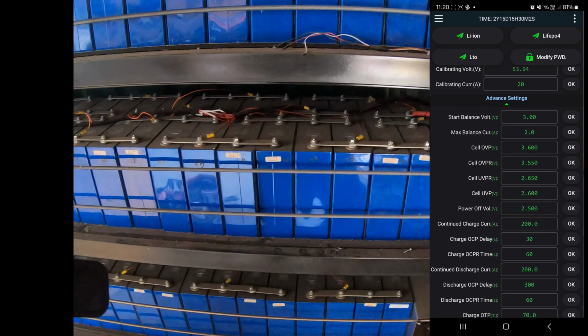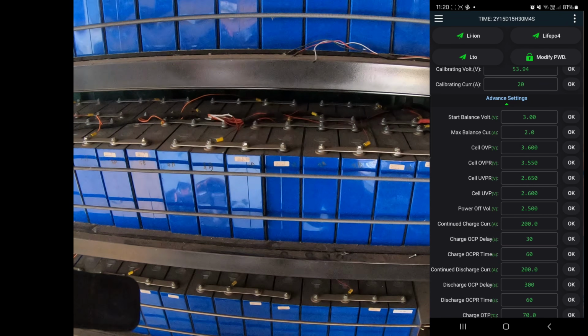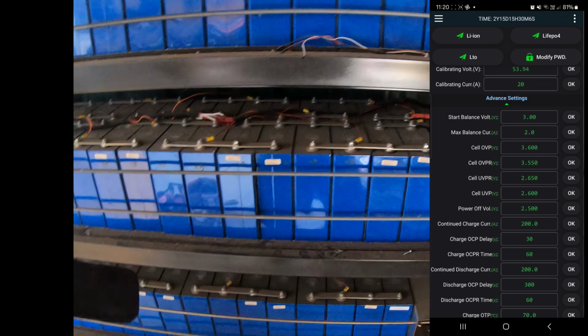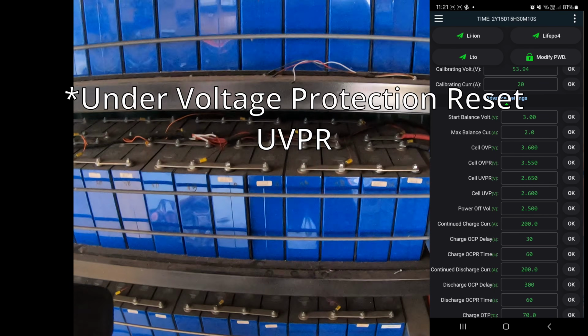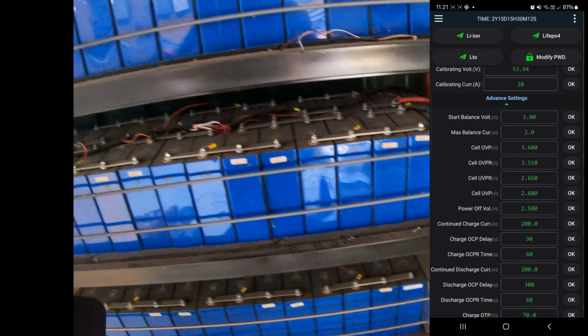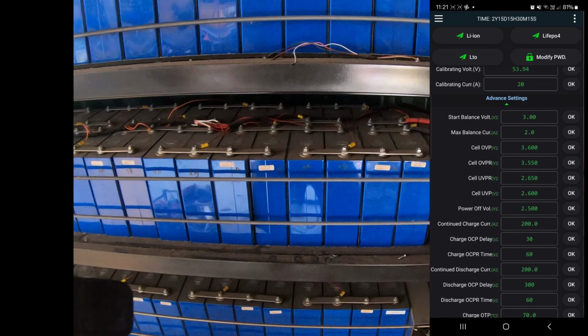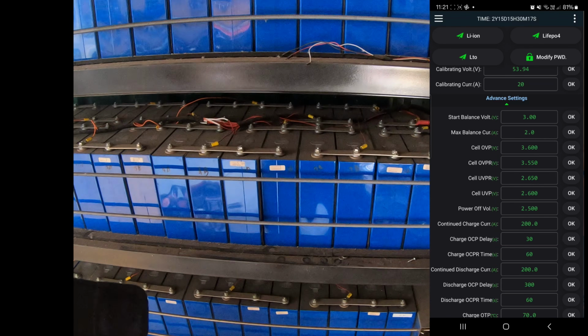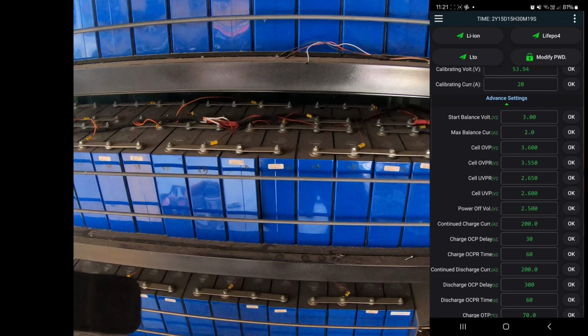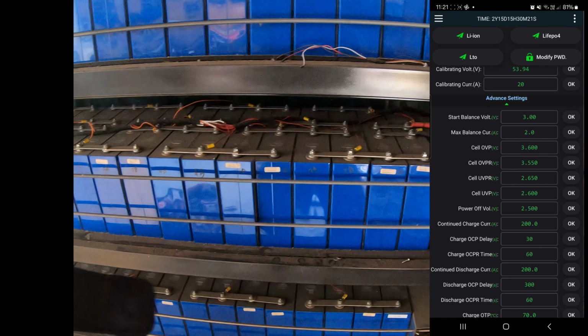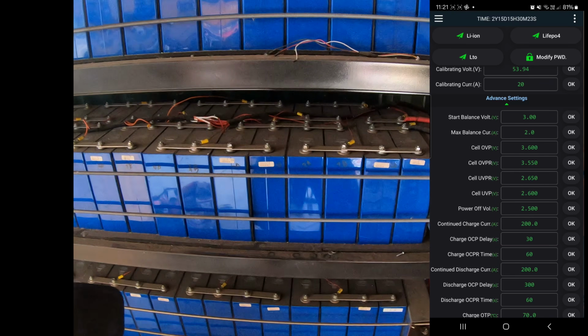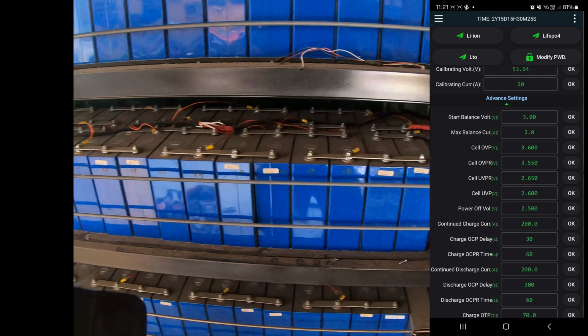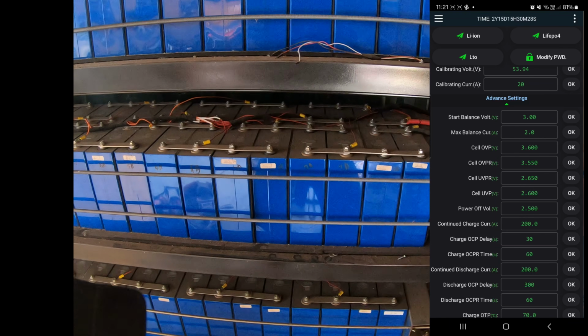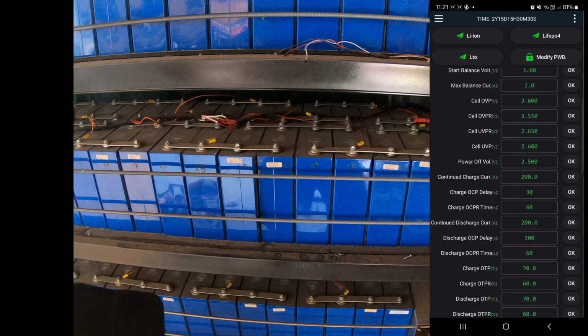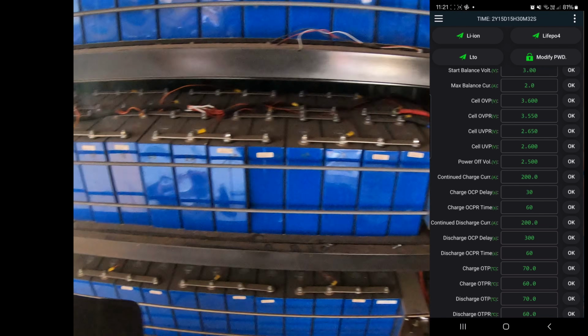So the next one is the cell under voltage protection, which is at 2.650, and in my opinion that's fairly low. I know some people will run them right down to 2.5 or even 2.45. Yeah, we're not super happy with that. So, oh, actually, hang on, I've got that around the wrong way. The cell under voltage protection is 2.6, but the under voltage protection reset is at 2.65. So when they rise to 2.65, after the load goes away, then that'll reset the under voltage protection. Power off voltage is set at 2.50.